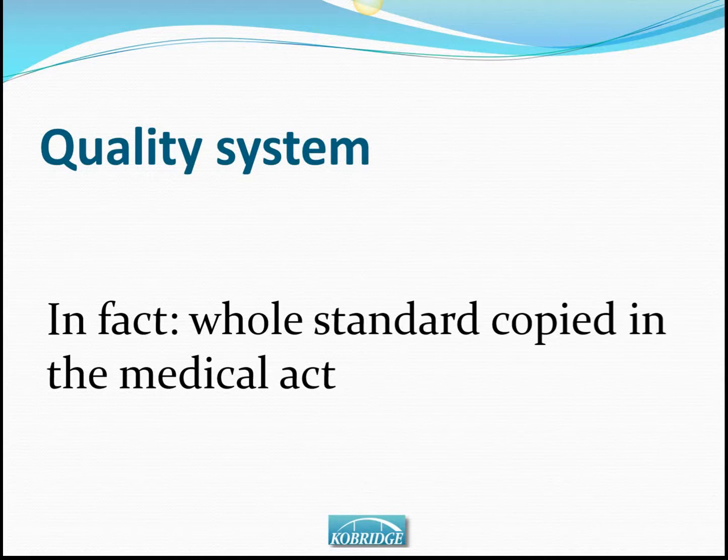If a company is compliant to the ISO 13485, then there should be no worries for the KGMP inspection. The focus should be on the preparation of the device master record, and that should be the only point that should be considered.